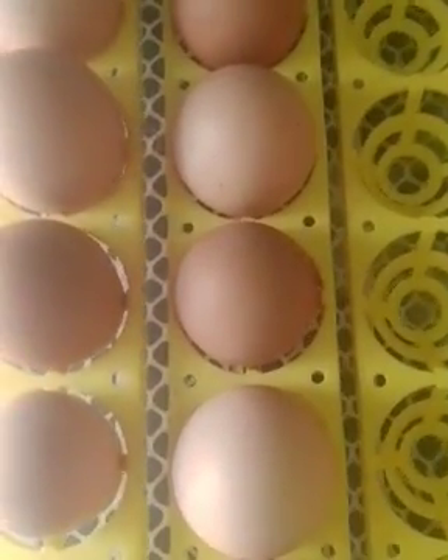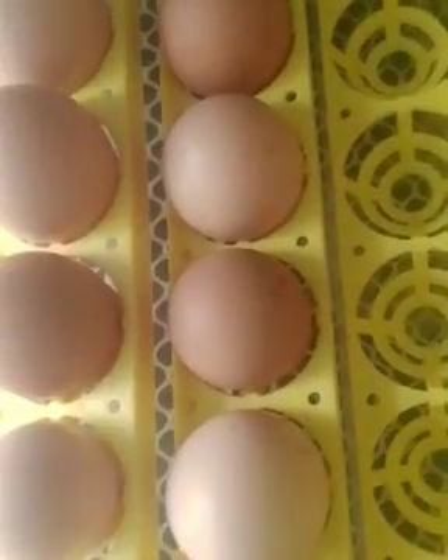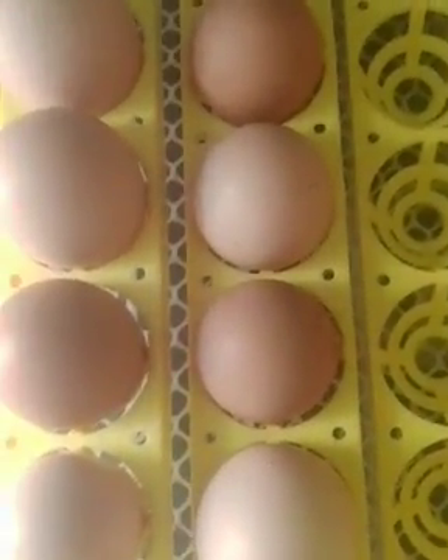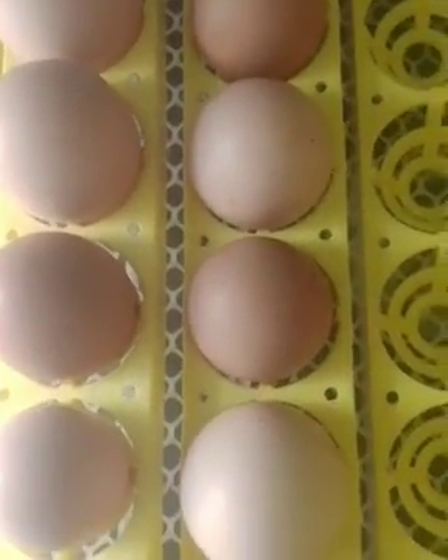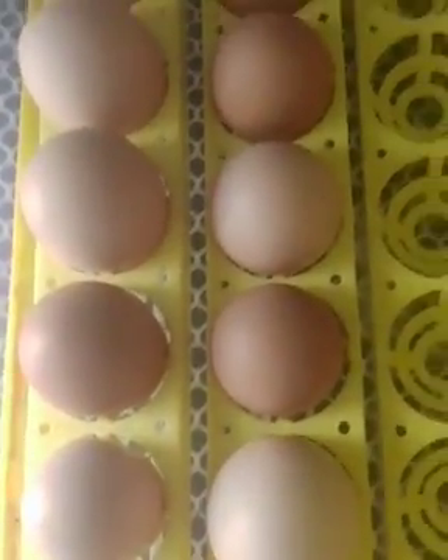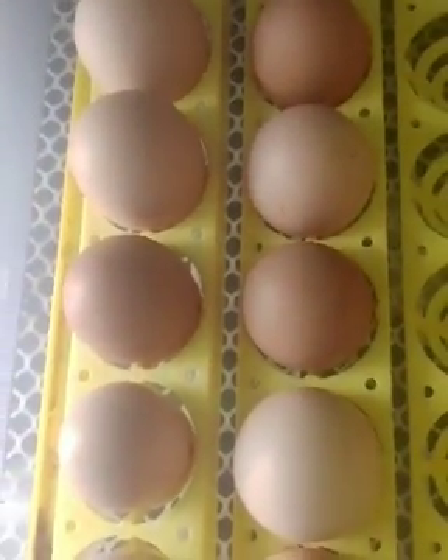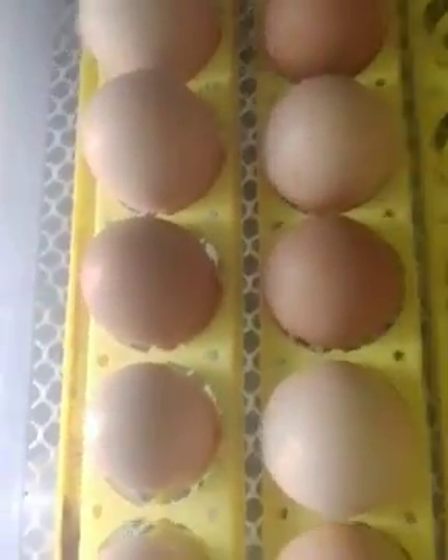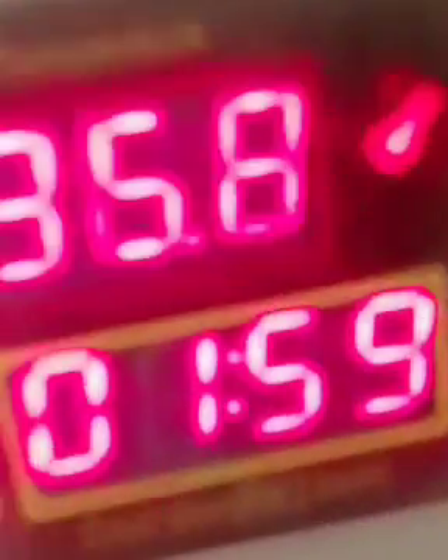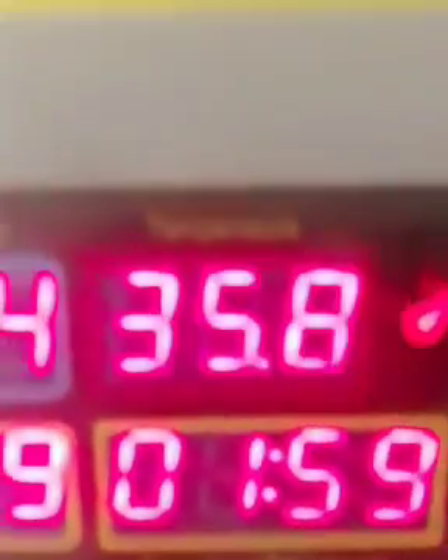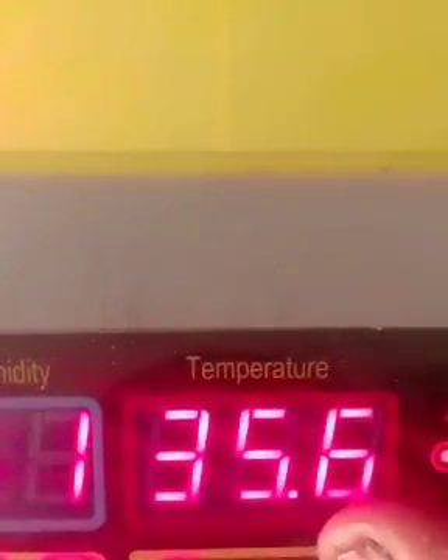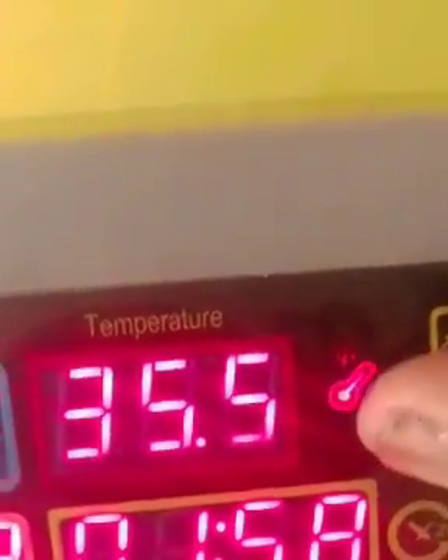This alarm you are hearing now, the incubator is telling you that something abnormal is happening in the incubator, because the incubator is not supposed to be open. So once it's open and the temperature is dropping below normal, the incubator will automatically alert you that something abnormal is happening. You can see it telling you low temperature, low temperature, low temperature. You can see the heater now trying to heat up, but because it is open, you can see it's open now.